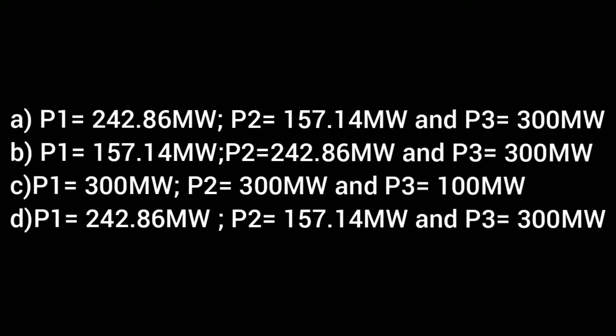If the plant is operating on economic load dispatch to supply the load power demand of 700 megawatt, the power generated by each unit is: option A, P1 is equal to 242.86 megawatt, P2 is equal to 157.14 megawatt and P3 is equal to 300 megawatt. Option B, P1 is equal to 157.14 megawatt, P2 is equal to 242.86 megawatt, and P3 is equal to 300 megawatt. Option C, P1 is equal to 300 megawatts, P2 is equal to 300 megawatts, P3 is equal to 100 megawatts. Option D is given as P1 is equal to 242.86 megawatt, P2 is equal to 157.14 megawatt, P3 is equal to 300 megawatt.